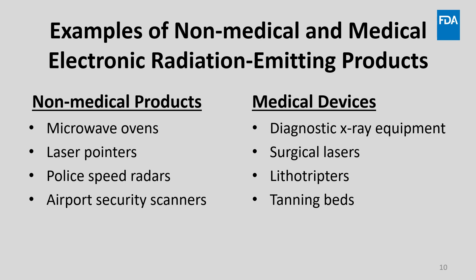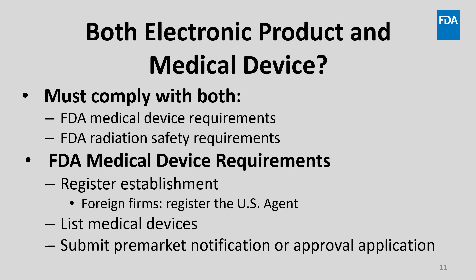Electronic radiation-emitting products may be either non-medical or medical. Examples of non-medical electronic products include microwave ovens used for food preparation, laser pointers, police speed radars, and airport security scanners. Examples of electronic products that are also medical devices include diagnostic x-ray machines, surgical lasers, lithotripters, and tanning beds. It's important to note that if your electronic product is also a medical device, it would be subject to FDA's medical device requirements in addition to our radiation safety requirements.